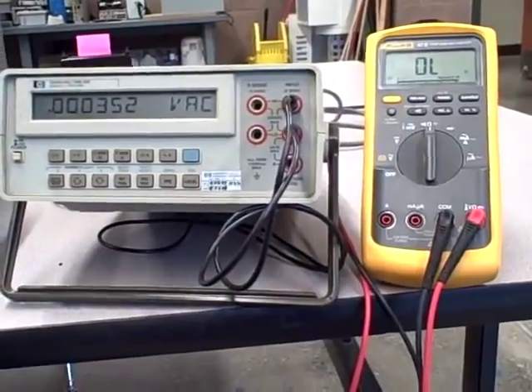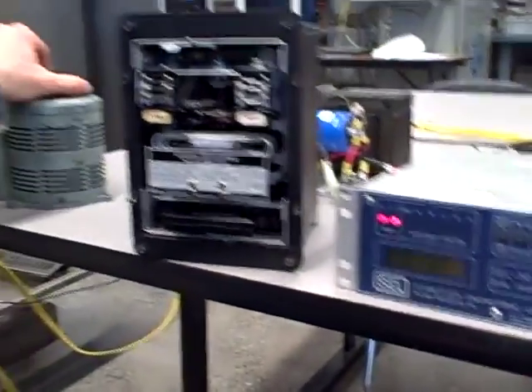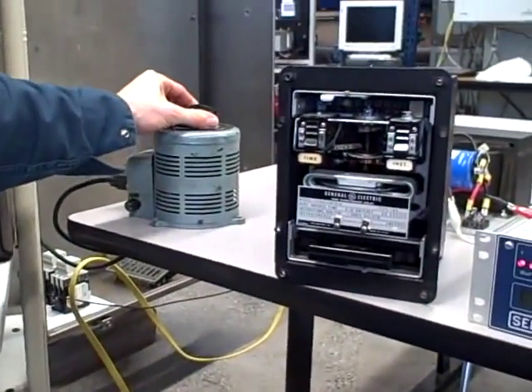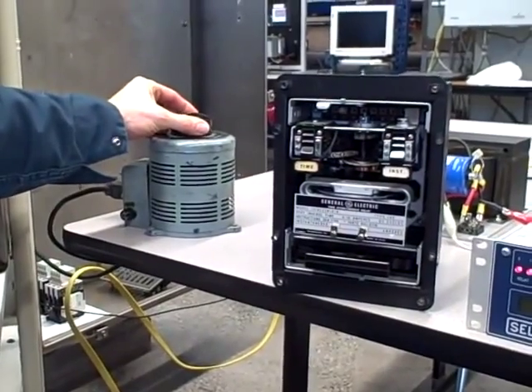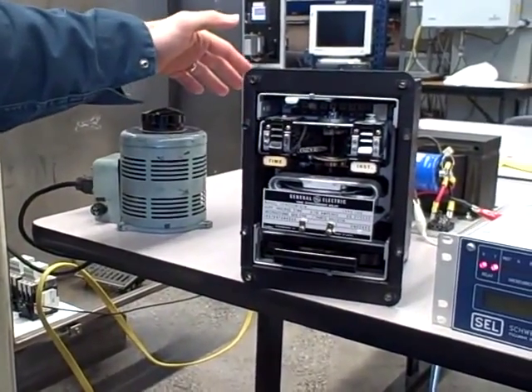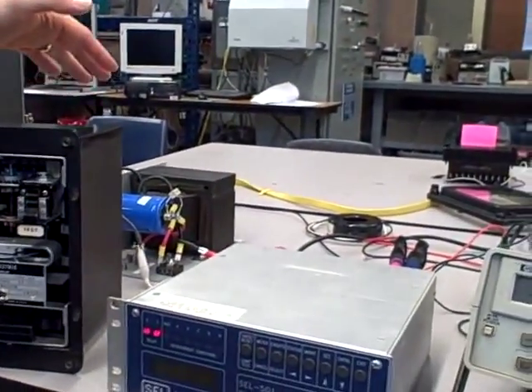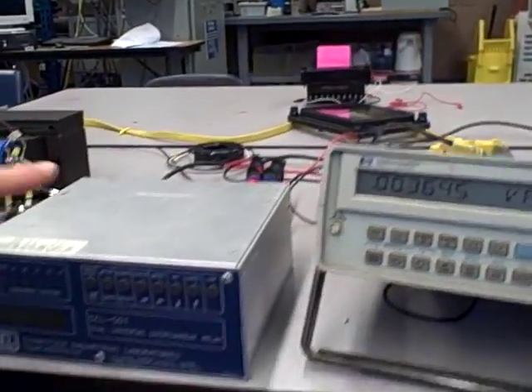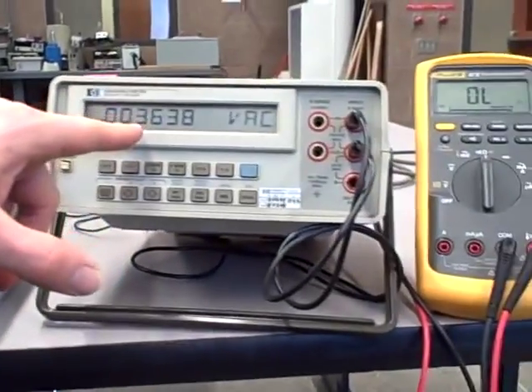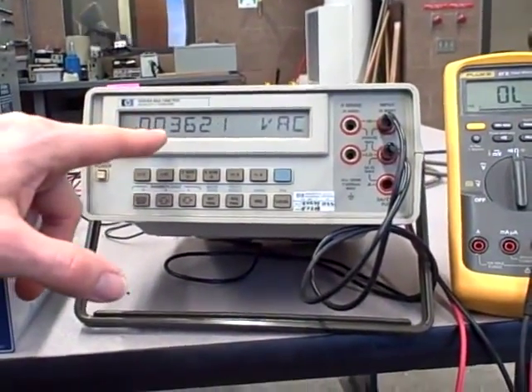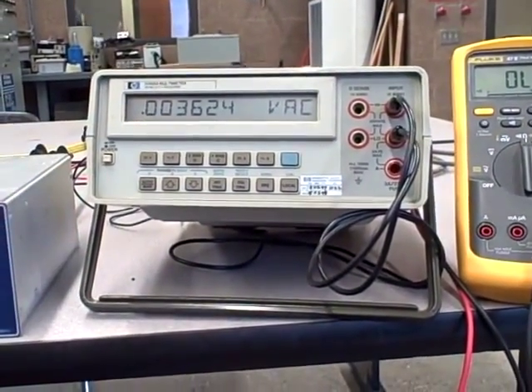So here we go. I'm going to adjust my current using the Variac transformer. I'm actually powering a step-down transformer, which powers another step-down transformer, creating my low voltage high current to go into the relay. And right now I'm measuring about 3.6 millivolts AC. Now with my 1 milliohm shunt, that corresponds to 3.6 amps AC of current into this relay.